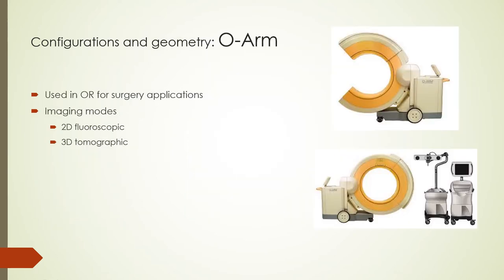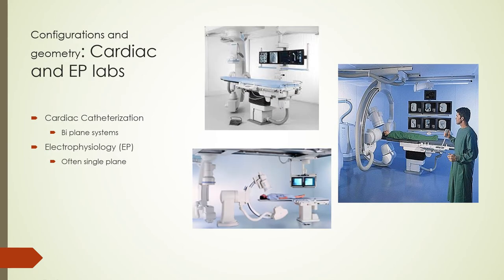Another type of configuration is the O-arm imaging system, used in operating rooms for guiding surgery applications like screw placements. The system is capable of imaging in 2D mode as a fluoroscope or in 3D mode to produce tomographic images. In 2D mode, doses are comparable to other fluoroscopy applications. The O-arm is shown opened to act as a C-arm or closed for 3D acquisitions. Dual tube and dual image intensifier systems are found in cardiovascular and interventional radiology suites, capable of rotation to create tomographic images like CT for navigation and guidance. The images show two biplane units for catheterization and a single plane for electrophysiology.